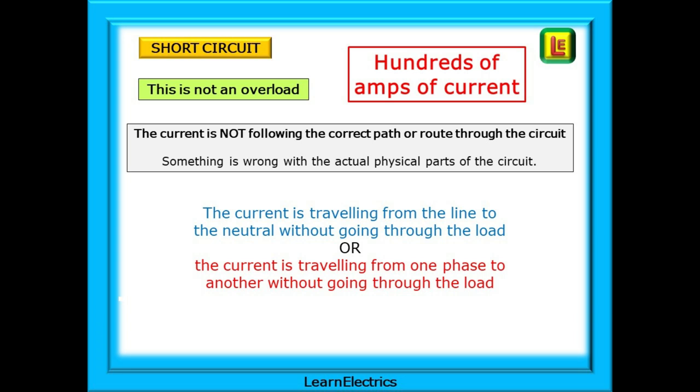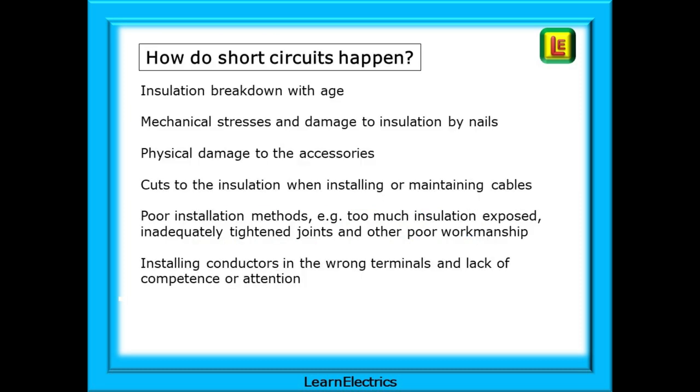How do short circuits happen? Well, how many ways can you get the line and neutral wires to touch each other? It could be insulation breakdown with age or mechanical stresses and damage to the insulation by nails. There could be physical damage to the accessories or cuts to the insulation when installing or maintaining cables. When we screw all the covers down, parts and cables may begin to touch. Poor installation methods can be a cause. For example, too much insulation is exposed or inadequately tightened joints and other poor workmanship that allows conductors to work loose and touch. And installing conductors in the wrong terminals and lack of competence or attention to detail are other causes.